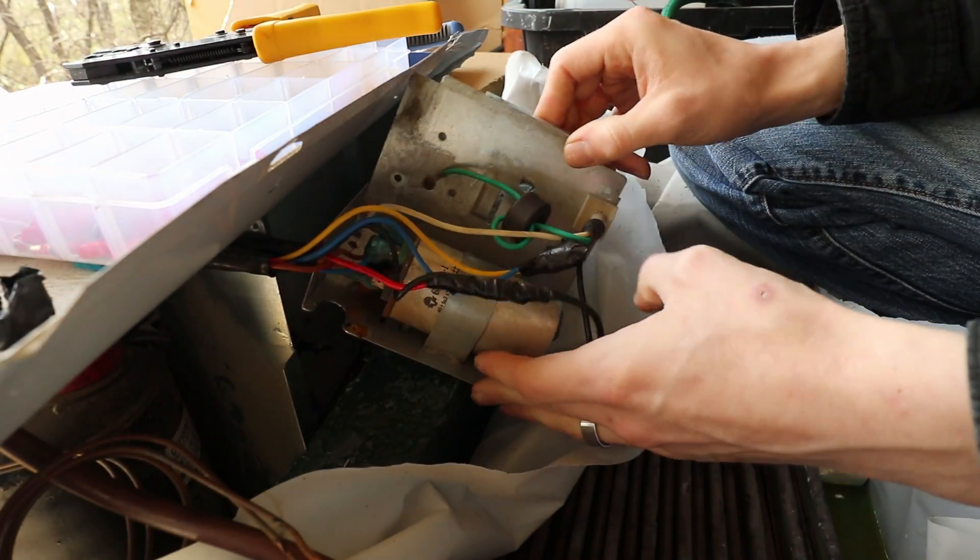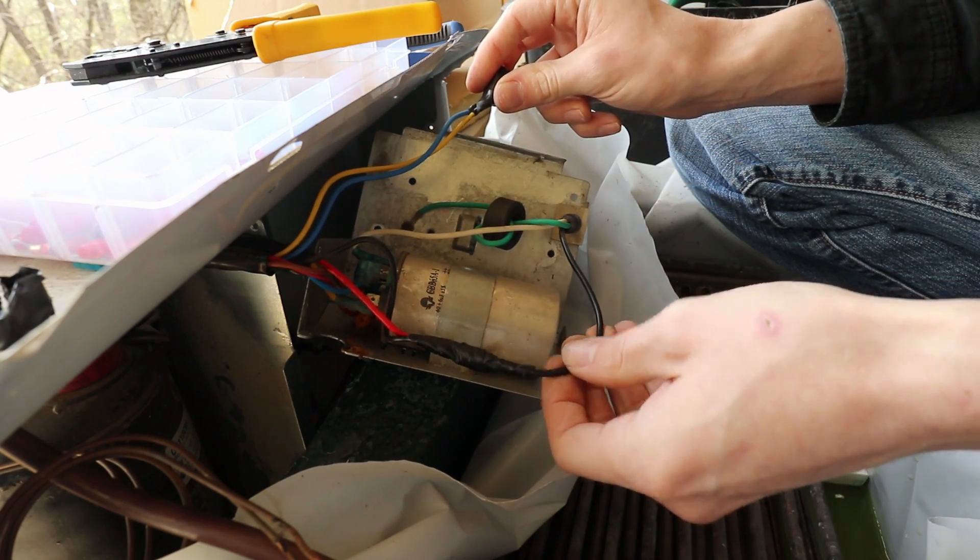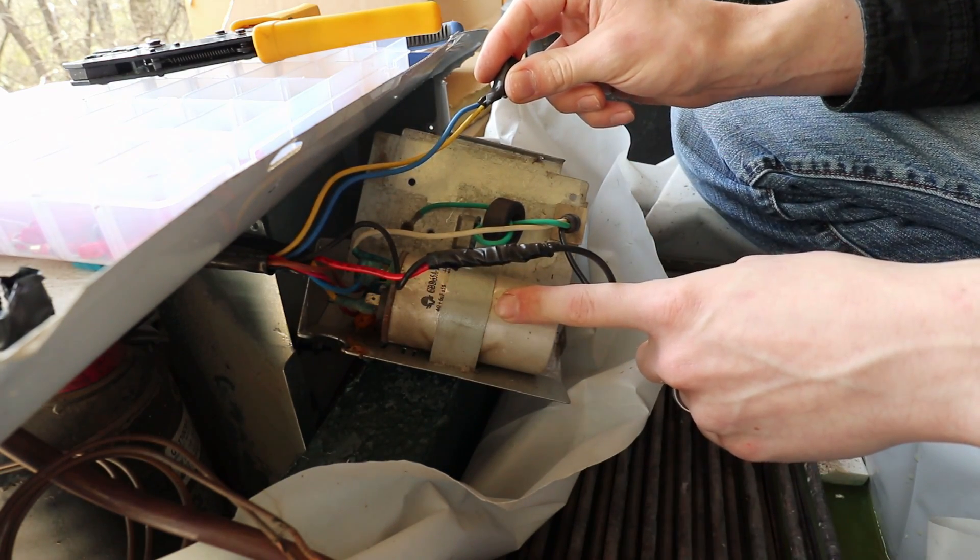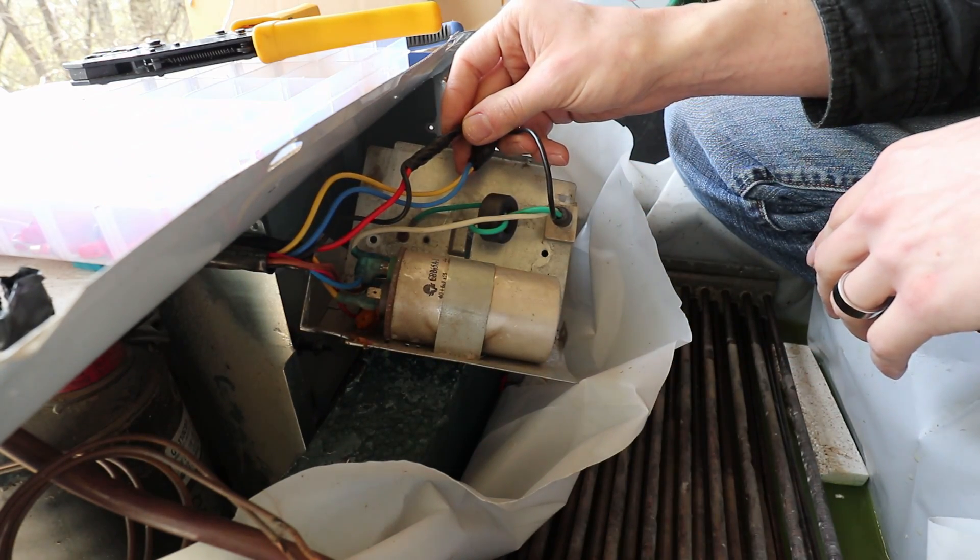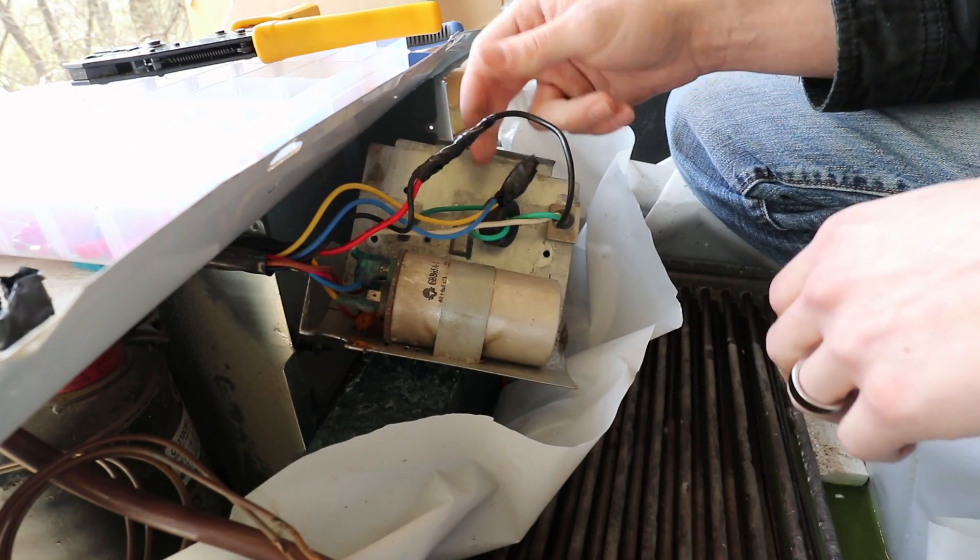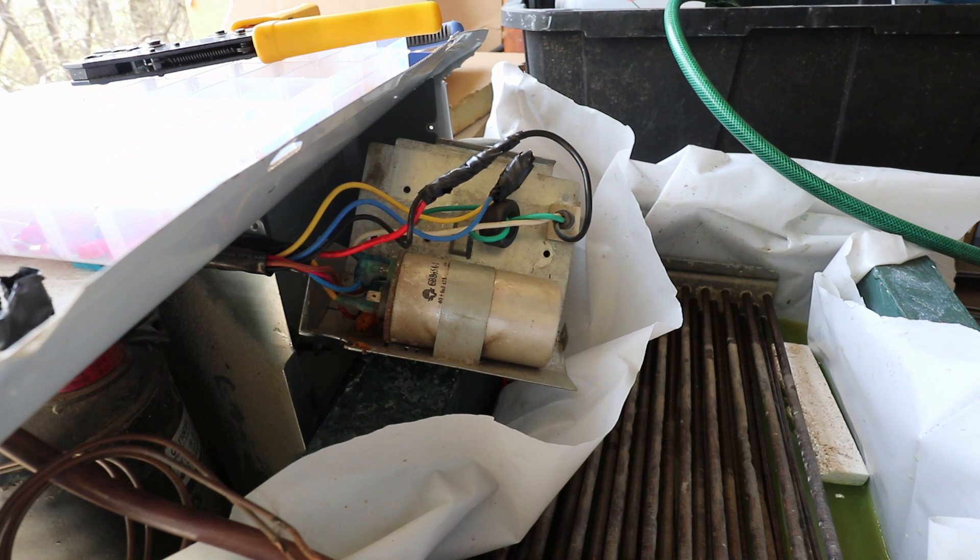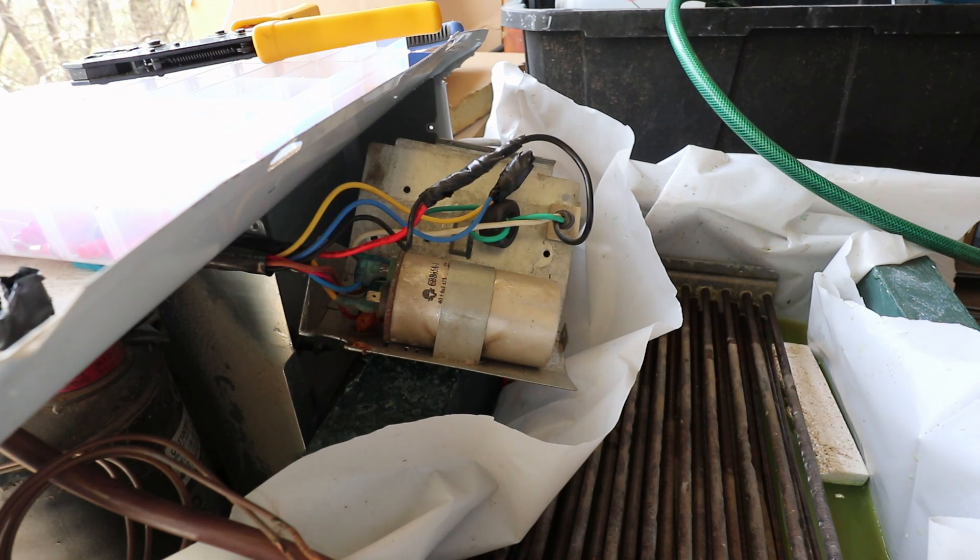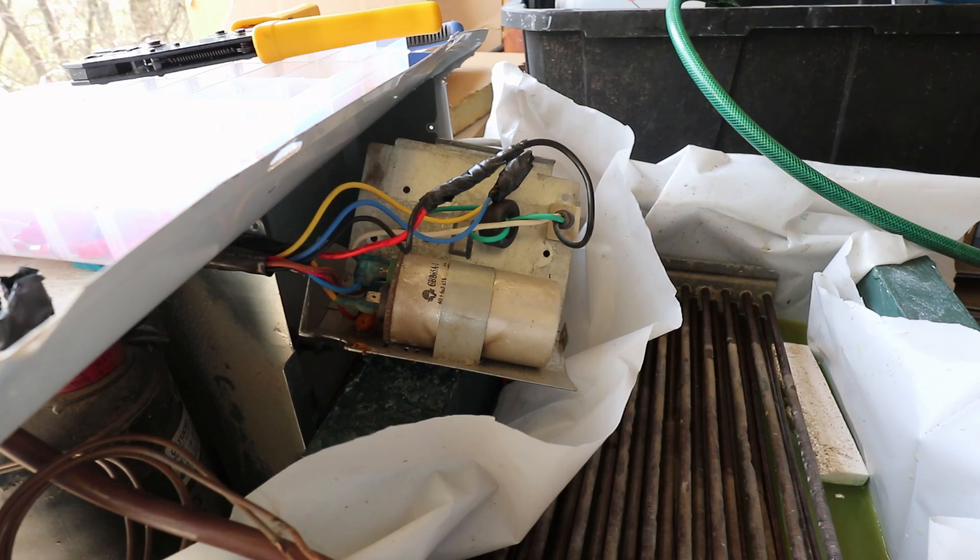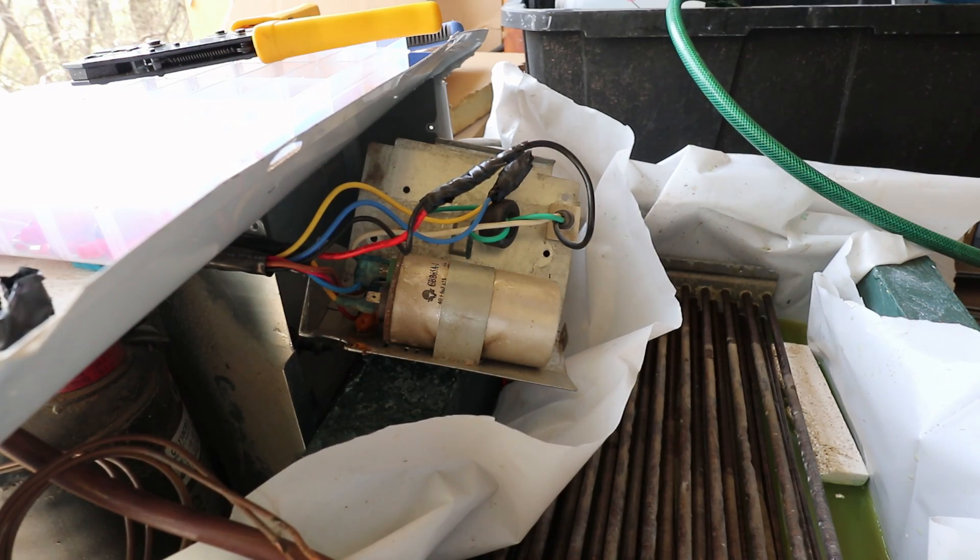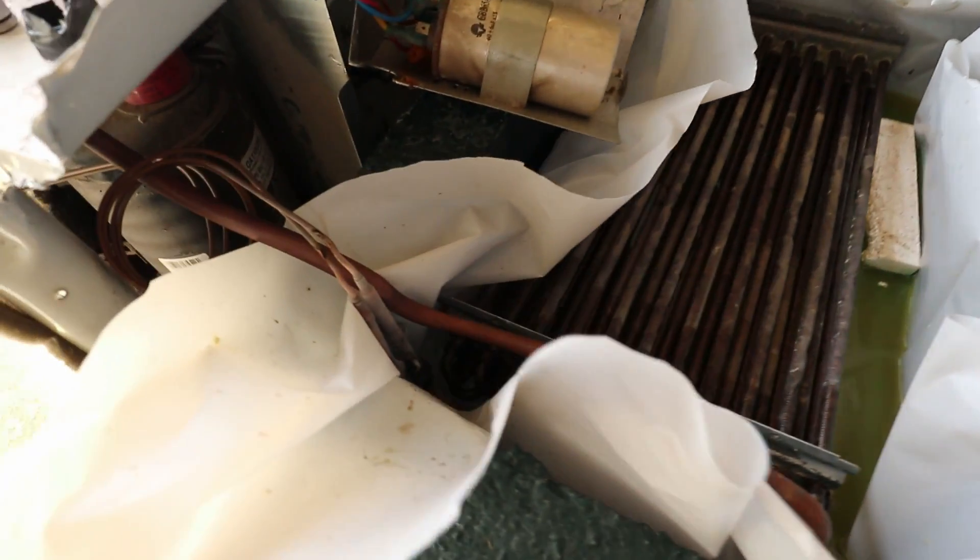Well, there we have it. All we've got now is the start and run capacitor and a couple taped up connections that had been properly crimped. So let's power it on again. We are plugged in. And here we go. You can see it's starting to frost up right there.